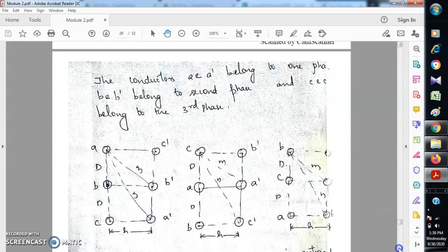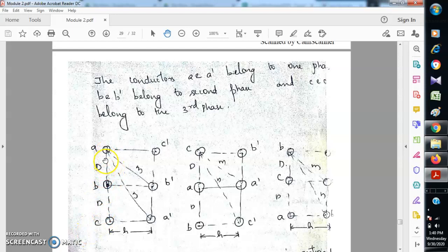Our aim is to space or place the conductors within a phase at maximum distance, and the distance between conductors between phases should be minimum. So it is placed like a, b, c so it has a minimum distance, and a to b and b to c will have the same distance, but the distance between a and c will be 2d.